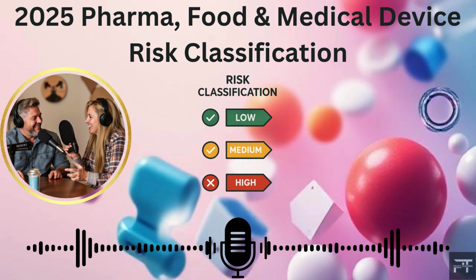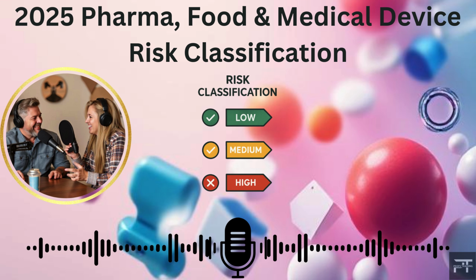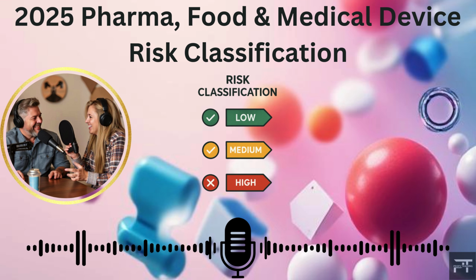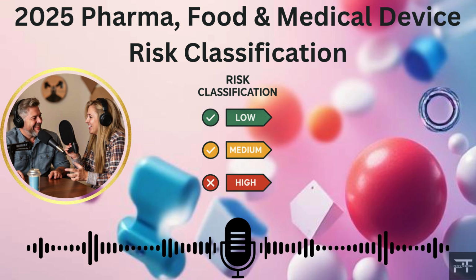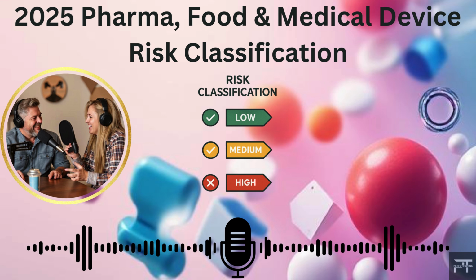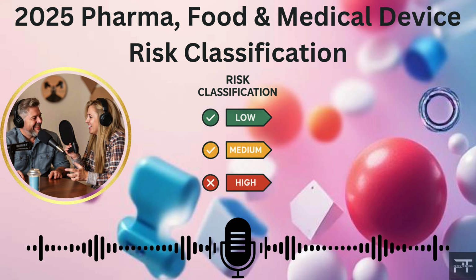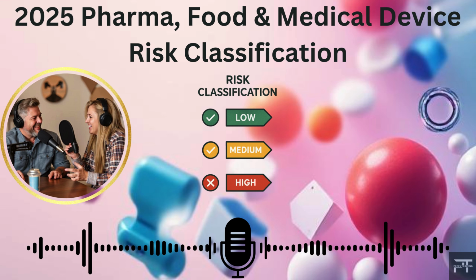For medical devices, the European Medical Devices Regulation, the EU MDR, is bringing in much stricter pre-market approval requirements, especially for those high-risk Class 2 and Class 3 devices we talked about earlier. We're also seeing an expansion of the Unique Device Identification System, UDI, to include not just single-use devices, but also reusable and even software-based medical devices. This will make tracking devices much easier throughout their life cycle and improve accountability. And with more and more medical devices being connected, there's a growing emphasis on strong cybersecurity protocols to protect them and the sensitive patient data they hold.